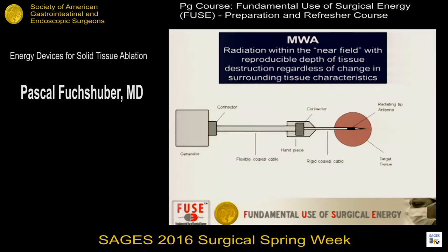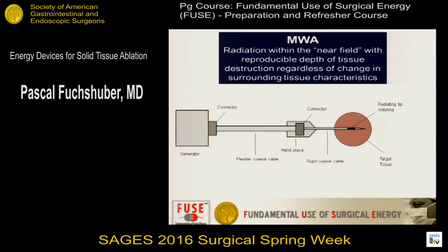Conceptually, the antenna consists of a generator, a flexible coaxial cable — just like the one used for your television — which has to be shielded, a handpiece, a rigid coaxial cable, and the radiation tip of the antenna, which is about a centimeter. The radiation within the near field where energy escapes from the antenna creates a reproducible injury at a reproducible depth of tissue, regardless of changes in the surrounding tissue.